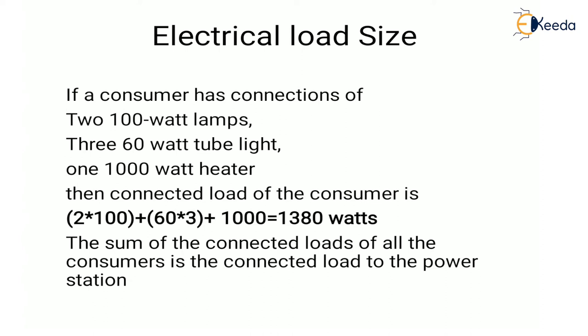Let us take an example on how to get electrical load size for a residential consumer. If a consumer has a connected load of 2 lamps of 100 watts each, 3 tube lights of 60 watts each, and a 1000 watt heater, then the connected load of the consumer is 2×100 + 3×60 + 1000, which equals 1380 watts.